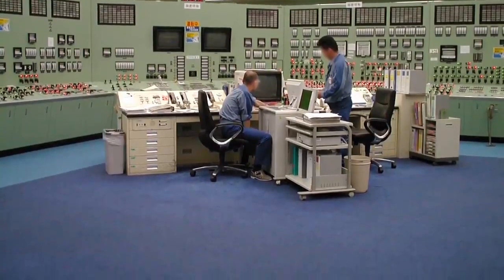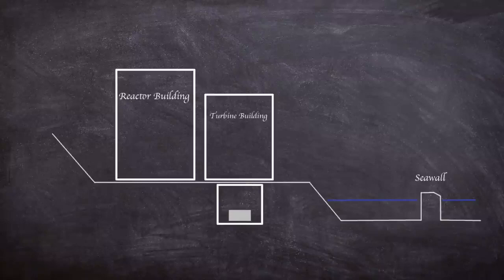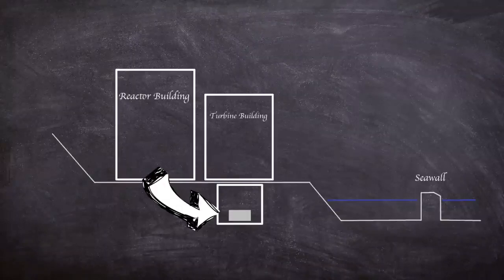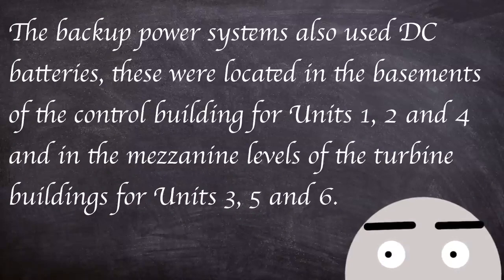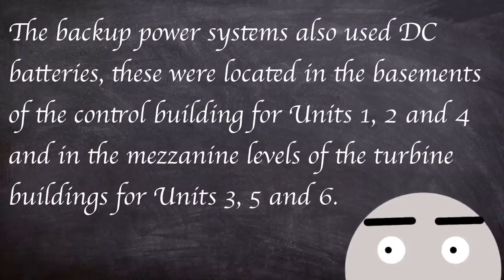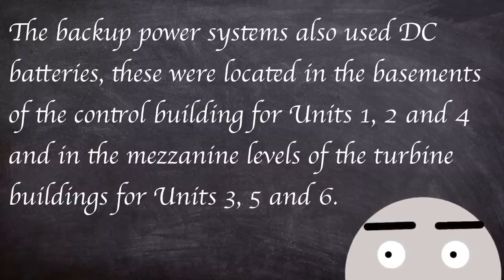Each reactor's emergency diesel generators and associated equipment were stored underneath the turbine buildings between seven to eight meters below grade. The backup power systems also used DC batteries. These were located in the basements of the control buildings for units one, two and four and in the mezzanine levels of the turbine buildings for units three, five and six.